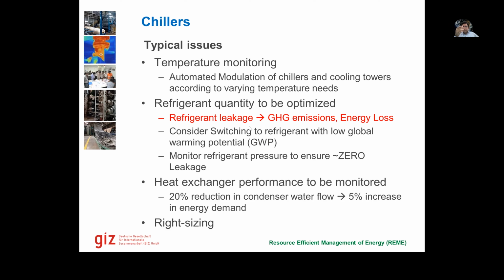They don't just dissipate. So there's a big energy loss when the refrigerant leaks, because we have to fill the refrigerant again. We have financial loss, but also very huge GHG emissions. It is important to continuously monitor the refrigerant pressure to ensure that there is zero leakage. Also, we should consider switching to refrigerants which have low GWP compared to those which we are currently using.